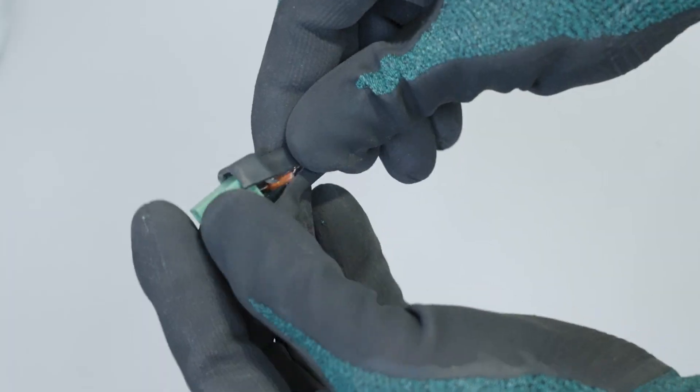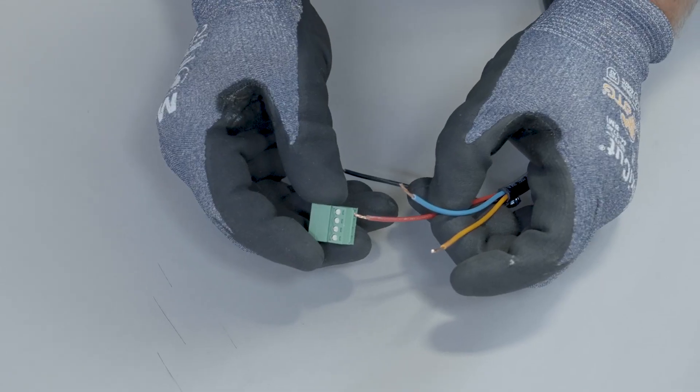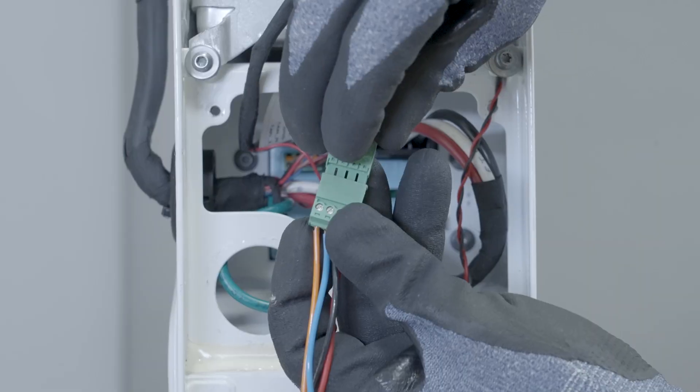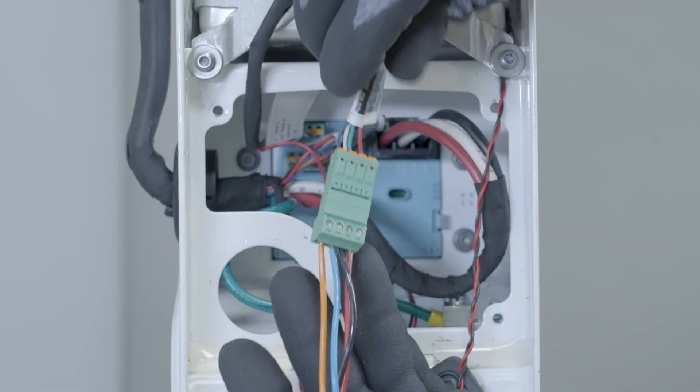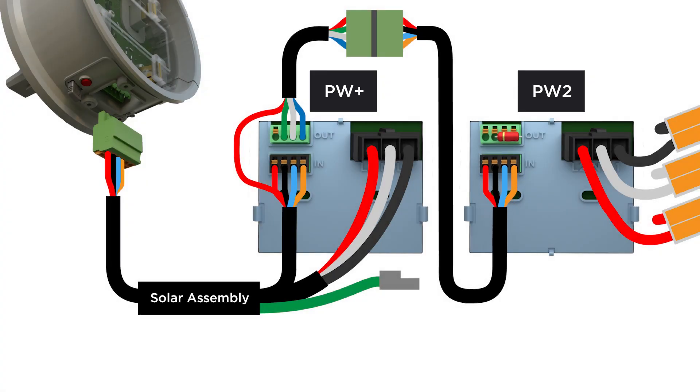Remove the black shrink wrap and discard the resistor. Connect a new four-conductor communication cable to the harness that previously had the end-of-line resistor. Connect the other end of this communication cable to the in port of Powerwall 2.